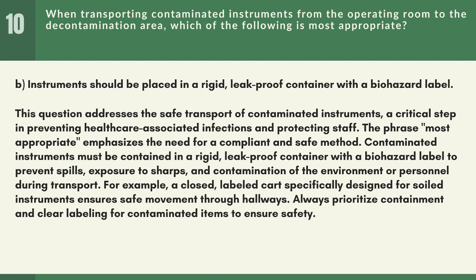Answer: B. Instruments should be placed in a rigid, leak-proof container with a biohazard label. This question addresses the safe transport of contaminated instruments, a critical step in preventing healthcare-associated infections and protecting staff. The phrase "most appropriate" emphasizes the need for a compliant and safe method. Contaminated instruments must be contained in a rigid, leak-proof container with a biohazard label to prevent spills, exposure to sharps, and contamination of the environment or personnel during transport. For example, a closed, labeled cart specifically designed for soiled instruments ensures safe movement through hallways. Always prioritize containment and clear labeling for contaminated items to ensure safety.